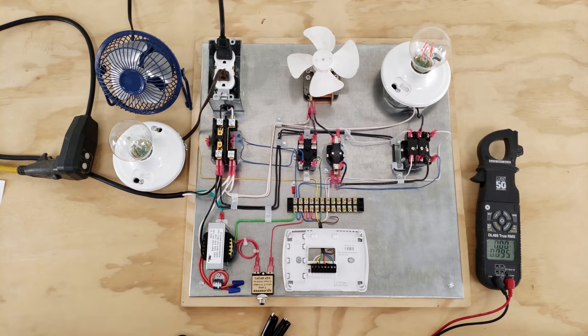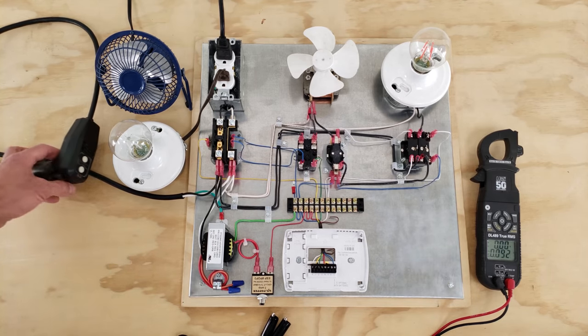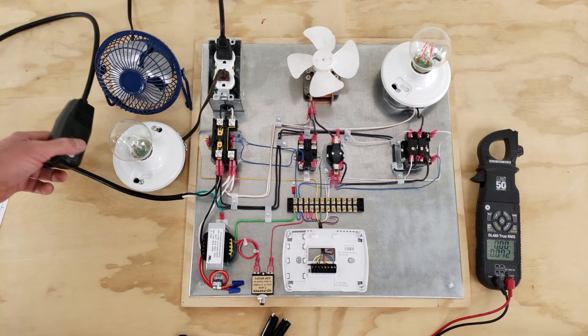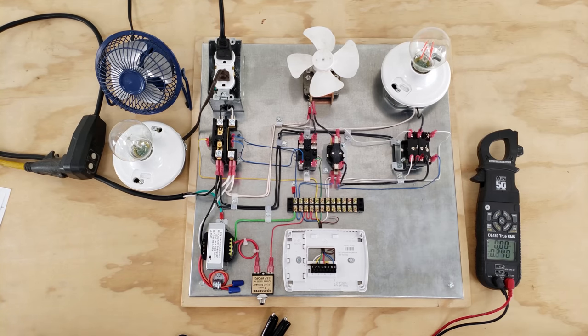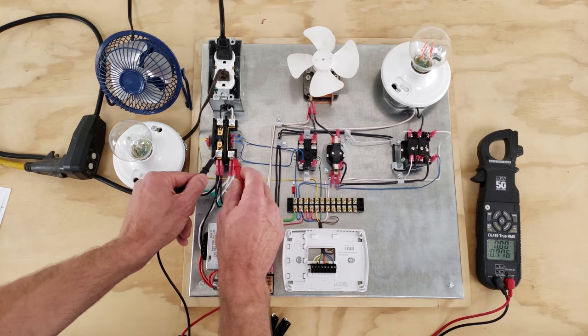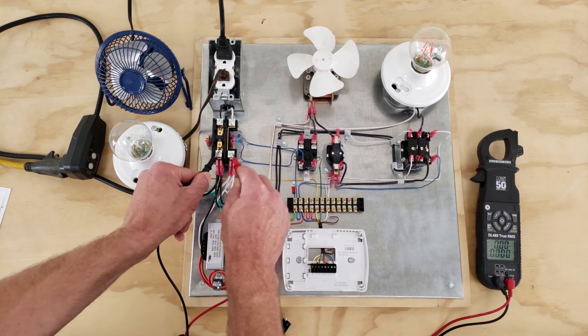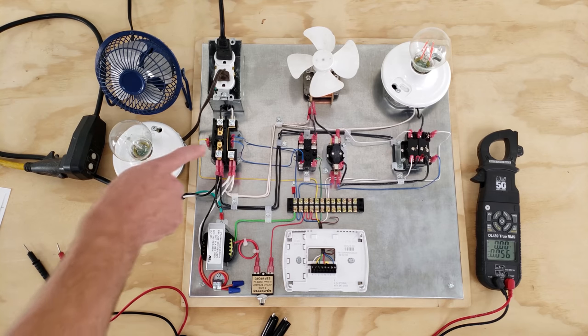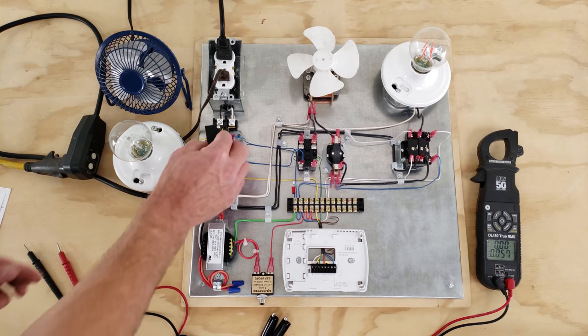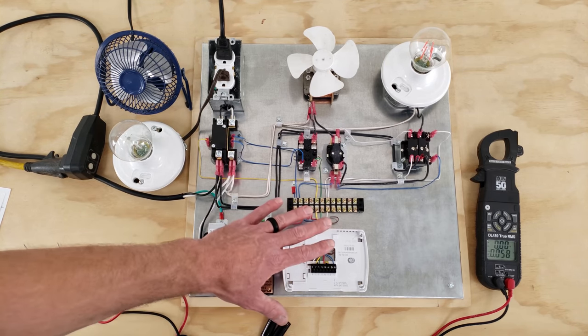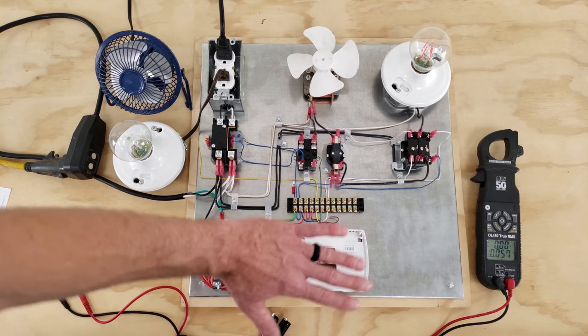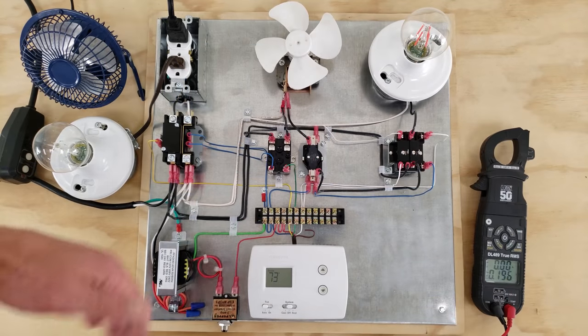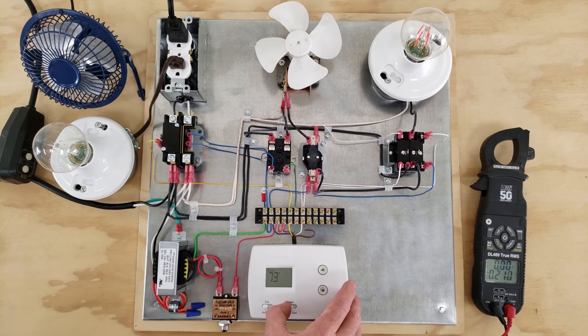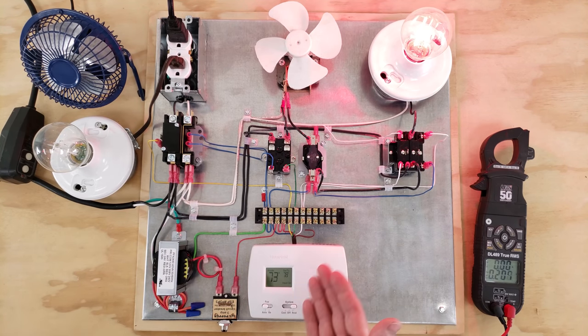So let's just go ahead and set up a problem. It's easy to shut this off. All we have to do is press our button right here. We can measure with our multimeter, and we just want to verify that we have no power. And so we can put a piece of rubber between the contacts right there. Now I'm going to set up a troubleshooting fault on this board, and we're going to have to determine what that problem is. This will be as if we're on a service call, and so basically we would want to turn on, say, the heat or the fan.